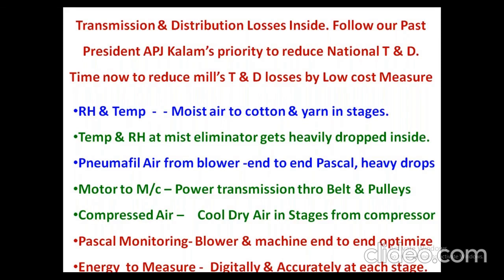Here you can find the transmission and distribution, whatever is done in the textile mill. We are trying to maintain almost 95% to 98% RH at the mist eliminator side of the humidification plant. But 98% RH maintained at the mist eliminator is not reaching the tail end of the mill. The transmission and distribution loss is more in the mill, especially on the humidification plant. If you are able to correct it, ultimately we have to replace the existing GI ducts and go for FRP ducts, especially circular ducts. Definitely this will see to it that whatever is done in the humidification plant will be straight away transferred to the mill premises in the spinning area, in the autoconer area, and in the blow room area as well. The temperature and RH at the mist eliminator heavily get dropped, because once it goes under the false ceiling, it is kept open. It has to be insulated. We go for a medium density insulation, MDF we say, and it has to be insulated.